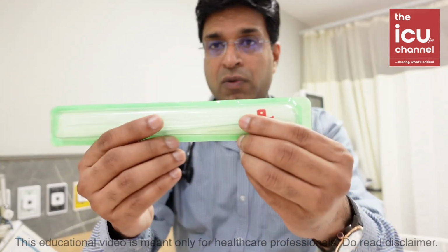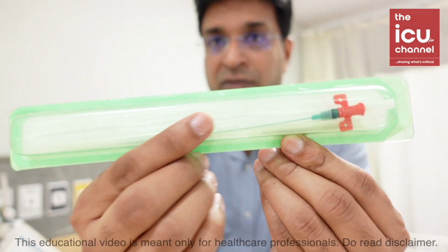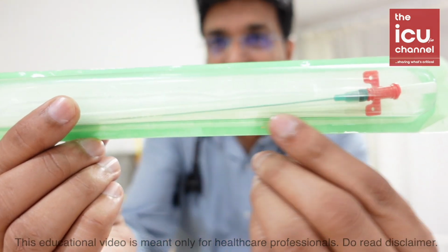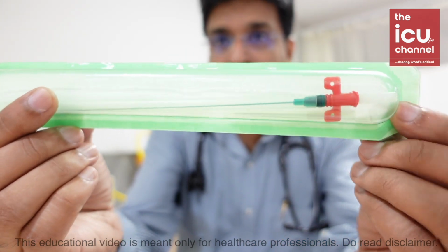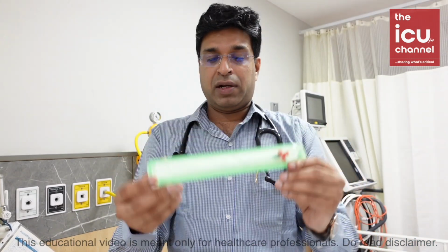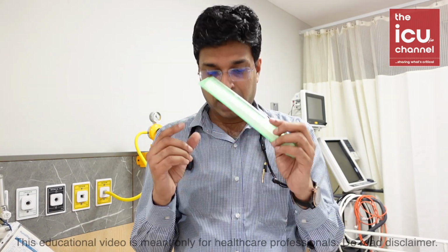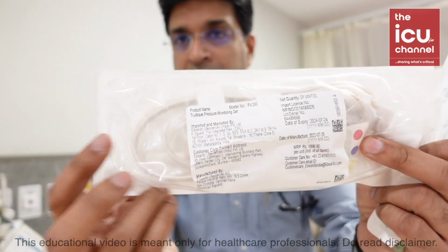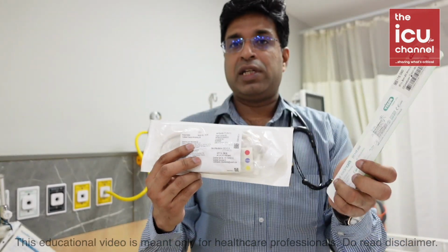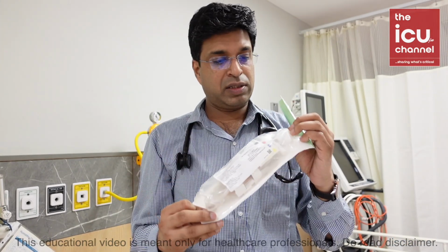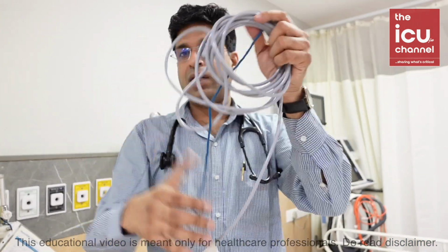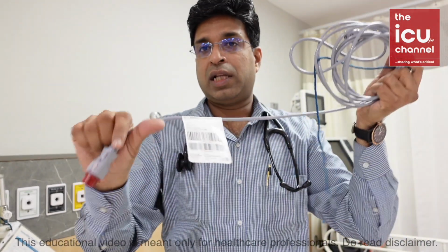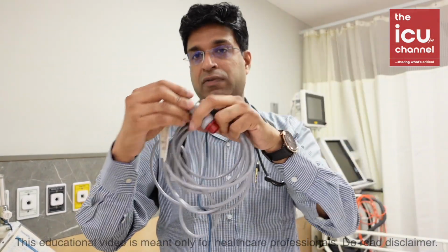It is a little stiffer than routine intracaths and has a guide wire also. When we insert this cannula, we connect it to a specialized circuit, the PMO line, which gets connected to a transducer here, and this gets connected to a cable that goes to the monitor. So this way one circuit is formed, and there is also a pressure bag to maintain a flush in the circuit.